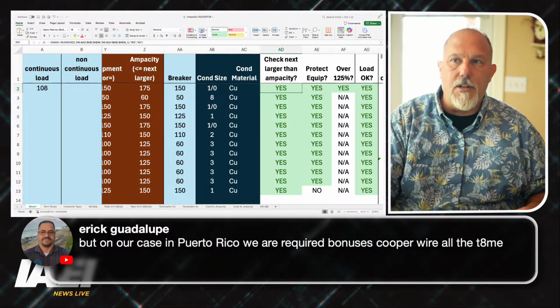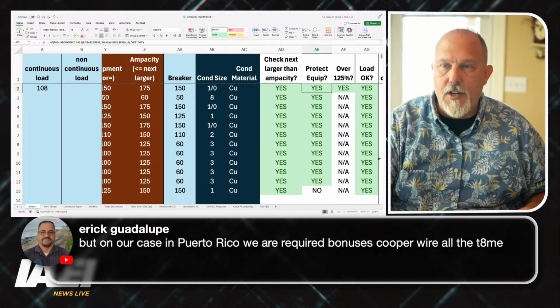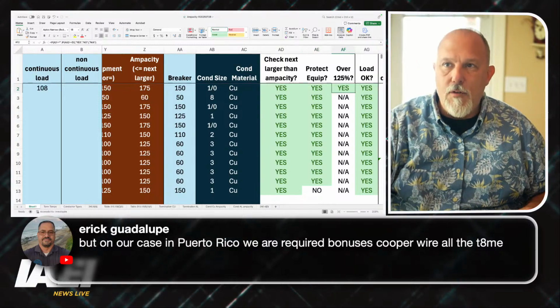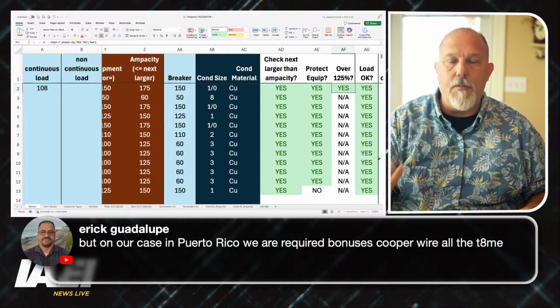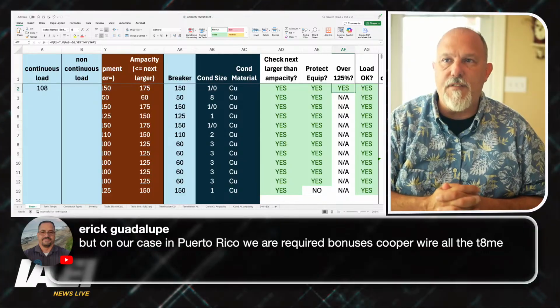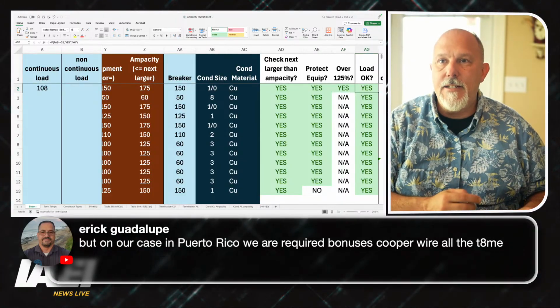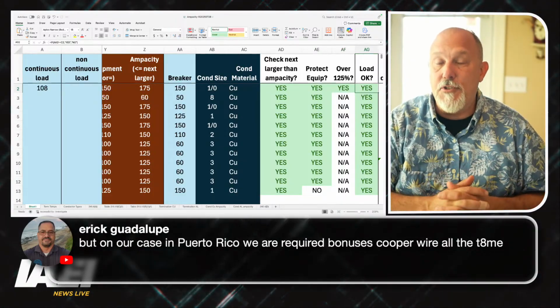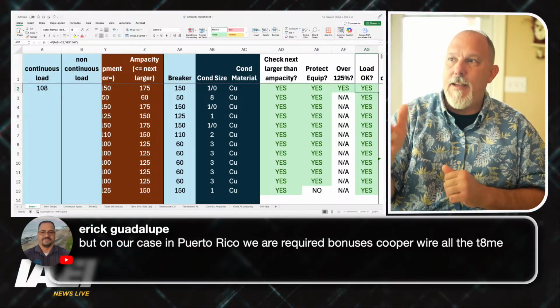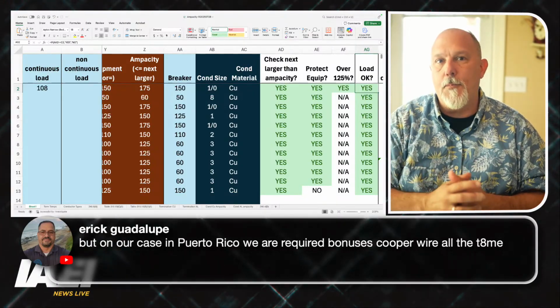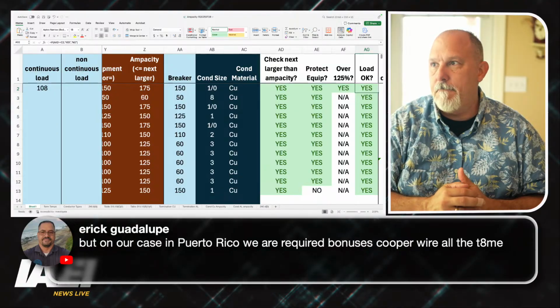I'm okay on the next larger than ampacity, I'm okay on the equipment protection, and I'm equal to or greater than the 125%. And I'm not less than the load current. So a 150 amp breaker would be appropriate for this application.